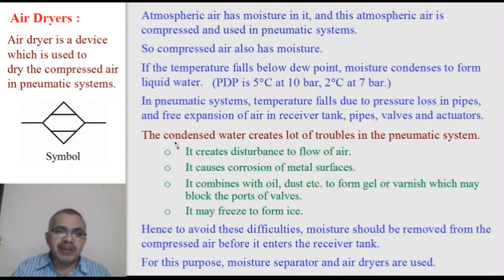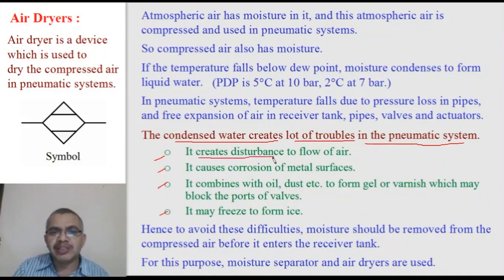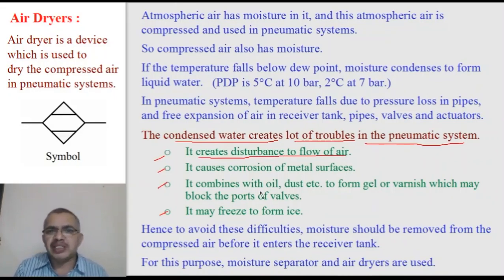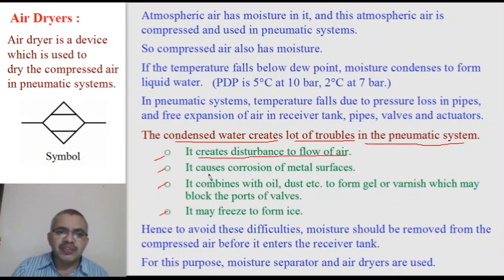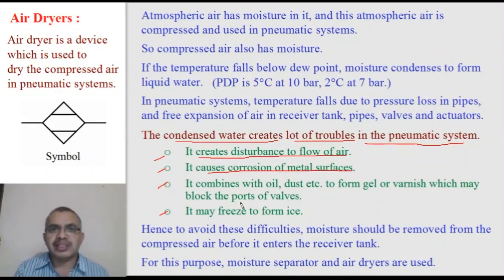The condensed liquid water creates several troubles in the pneumatic system. First, water creates disturbance to the flow of air — air cannot flow easily if water droplets or bubbles are present in the pipe. Second, water causes corrosion of metal surfaces such as pipe walls and cylinders, and rust may form.